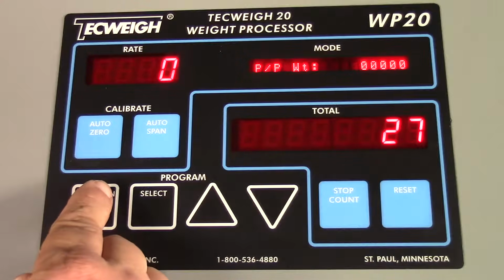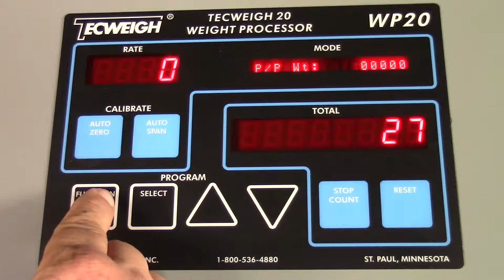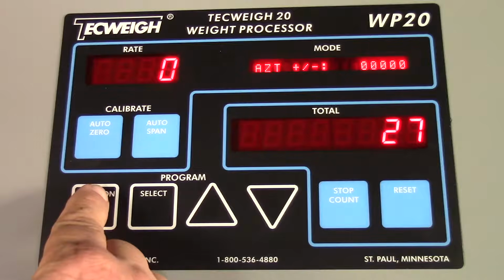That's where we might do a material test and enter the value in there, the pre and post weight. You can find all this in the manual too. AZT, we're not going to change that for right now, but it's called auto zero tracking. That would allow us to help hold the zero just on the display a little better.